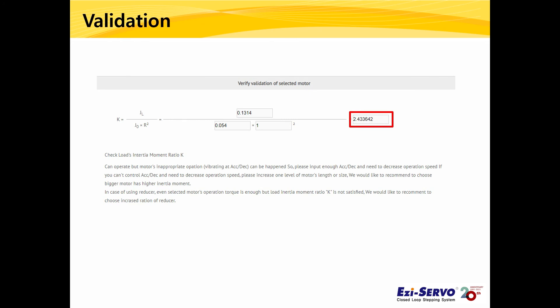Finally, let's verify the motor selection by calculating the moment of inertia ratio k, which is obtained by dividing the inertia of the load by the inertia of the rotor. If it exceeds the recommended ratio, the motor may step out, stop, or vibrate. Typical stepping motors allow inertia ratios from 1:5 to 1:10, whereas closed-loop stepping motors allow up to 1:30. It is not recommended to exceed a ratio of 30. If the ratio does exceed 30, use a larger motor or gearbox to reduce it. In this case, the inertia ratio is 2.43, so the 42M motor is suitable for this example system.